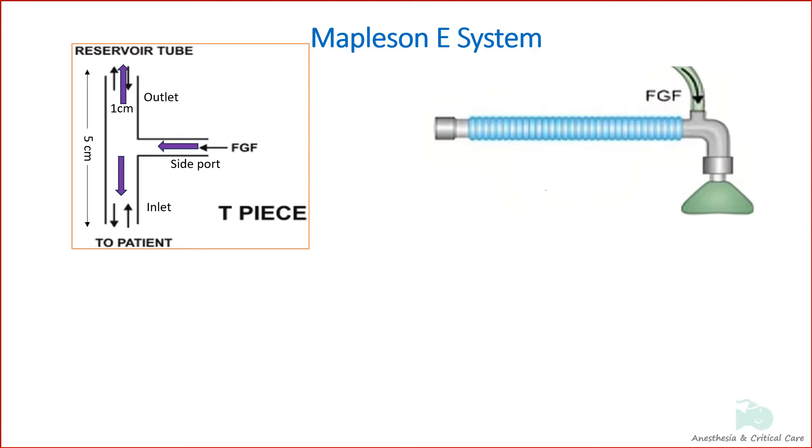Mapleson E system is derived from Ayre's T-Piece configuration by adding tubing to the expiratory part of the circuit that acts as a fresh gas reservoir during inspiration.